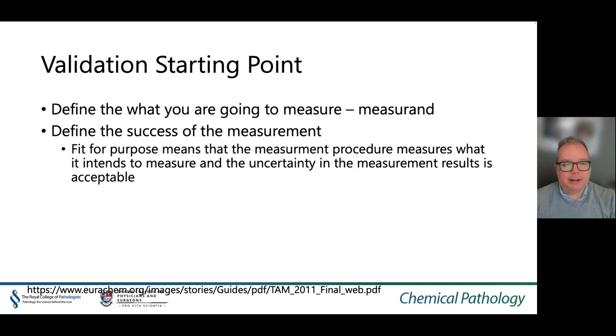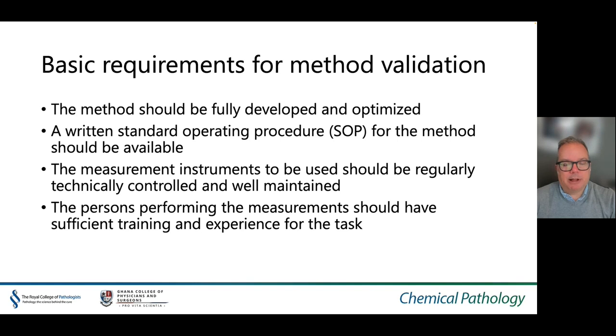The first point in any validation exercise is to define what we are going to measure — the measurand — and to define the success of the measurement. Fitness for purpose means that the measurement procedure measures what it intends to measure and the uncertainty in the measurement of results is acceptable. The method should be fully developed and optimised, a written standard operating procedure should be available, measurement instruments should be regularly controlled and well maintained, and persons performing the measurements should have sufficient training and experience.